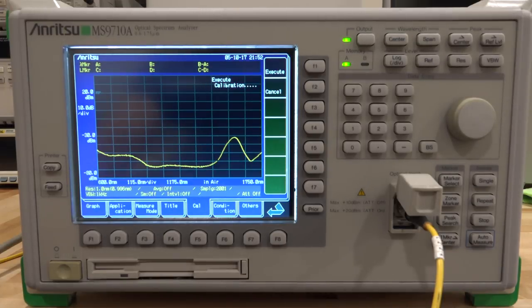But I can hear the stepper motor and the grating motors and all the alignments going in the background, so it's definitely doing some sweeping, trying to get this calibration working. Jeez, it really does take its time, doesn't it? There we go, it succeeded. It actually only took another 5 seconds after I stopped the video. So yeah, it succeeded the calibration, which means I'm assuming that it was satisfied with it.